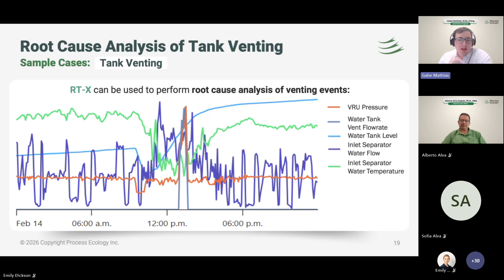And then lastly, we can look at the temperature of the inlet separator just to see if that slug is overwhelming the process. And we see that the inlet heater is not able to keep up with the heating demand on that water because it's February 14th, it's quite cold outside. So we went from not only event detection to quantification and root cause analysis. And then we took it one step further. For the entire month, we decided to see how many of these events we saw, and then how many liquid slug events, if we want to call it that, we saw.